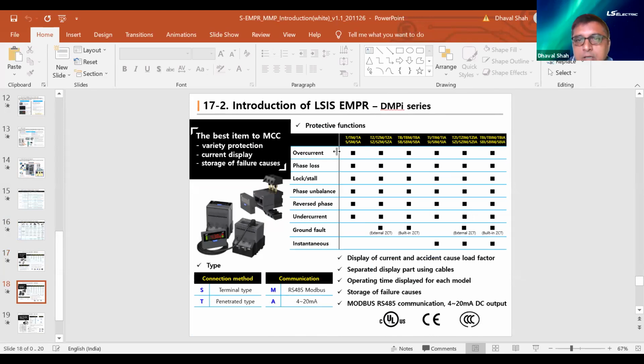So moving ahead, again, this is the hot selling product, or you can say the champion of the product, like in case of cars, what we call Swift. Similarly, DMPi is the most hot running product which serves most of the purpose of all the industries. So you have basic functionalities of overcurrent, lock rotor current, phase unbalance, reverse phase, undercurrent, and ground fault inbuilt in almost all the product range. Only a few things would vary, like the instantaneous protection in some of the products. And there would be terminal type connection, penetrate type of connection, and Modbus or 4 to 20 milliamps output is also available. Again, as I mentioned, UL, CE, and CCC. These basic certifications would always be available in all the products.